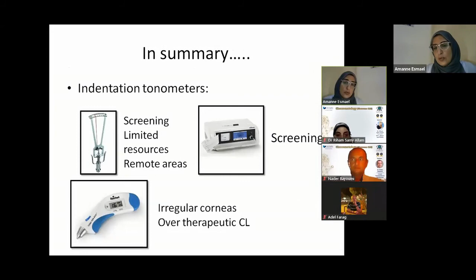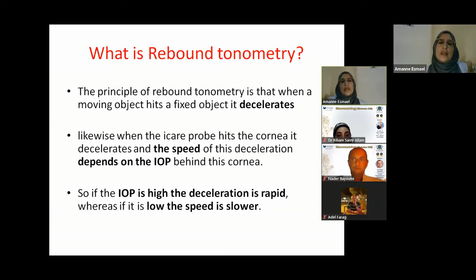Now, the second part of this presentation is concerned with rebound tonometry. The principle in rebound tonometry is that a moving object, when it hits a stable object, will decelerate. What rebound tonometry does is measure the speed at which the moving object, or the probe of the instrument, decelerates. So if you are confronted with a high intraocular pressure, the deceleration will be rapid, and if you're confronted with a low intraocular pressure, the deceleration will be slow. Rebound tonometry was introduced in 1997, probably that's not long.